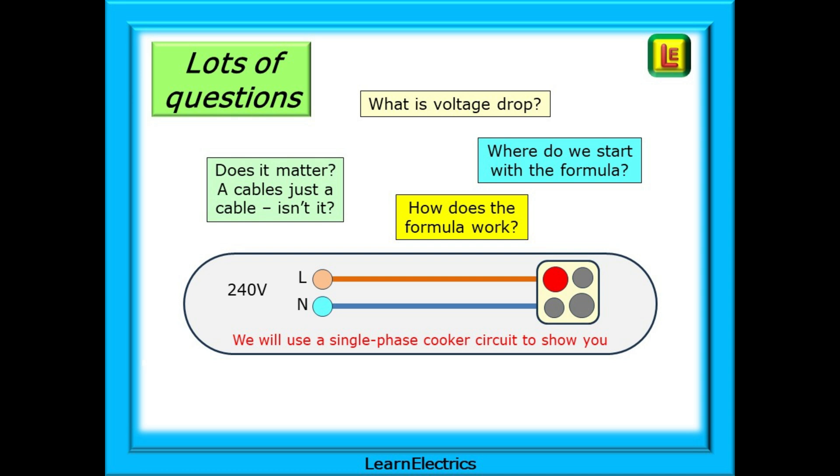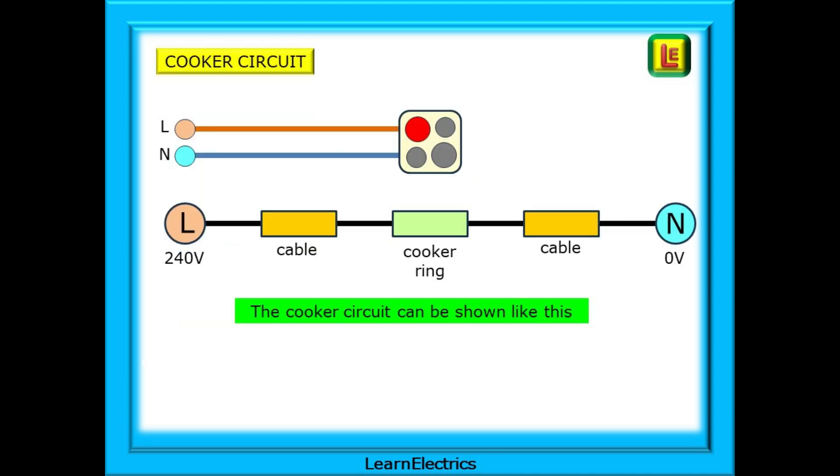A cable is just a cable, isn't it? We will use a basic cooker circuit to show you voltage drop and its effects on the circuit. The cooker here has a line from the consumer unit to the cooker, and a return path along the neutral. There will also be an earth or CPC, but we do not take this into account for voltage drop calculations.